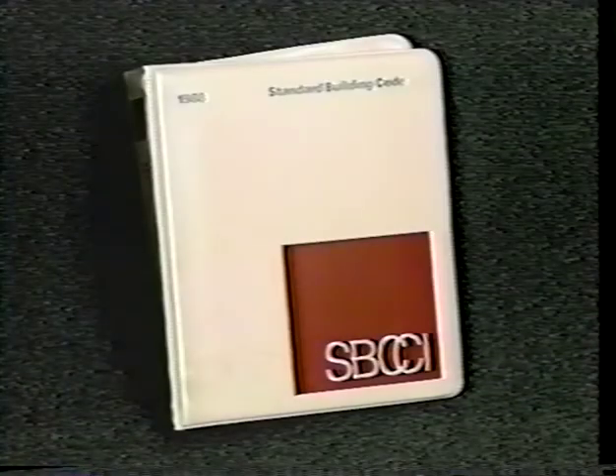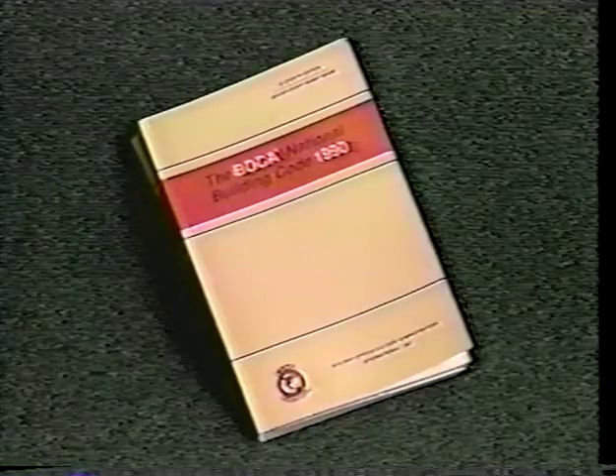However, about the only thing most people have to refer to are fire safety test results published in a variety of building codes. Tests like the Steiner Tunnel Test, which attempts to determine how much smoke the burning material creates. The Horizontal Burn Test, which reveals how quickly the flame spreads over the material's surface. And the ignition test, which determines how easily the material will catch fire and sustain combustion. But these fire safety codes may not tell the whole story, or they may be misapplied or misunderstood.